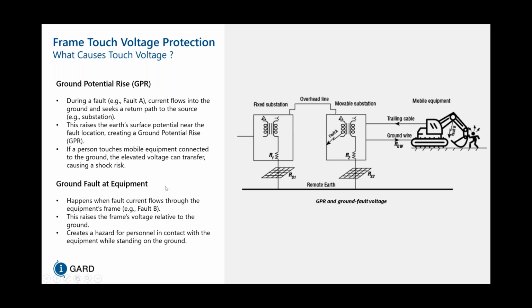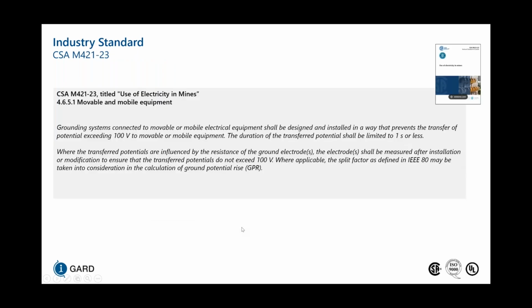The second method is if there's a ground fault at the equipment over here where fault B is indicated. In this case, there would be a touch potential between the energized equipment as well as ground, and as a result, an electrical shock can occur and create a hazard for personnel.